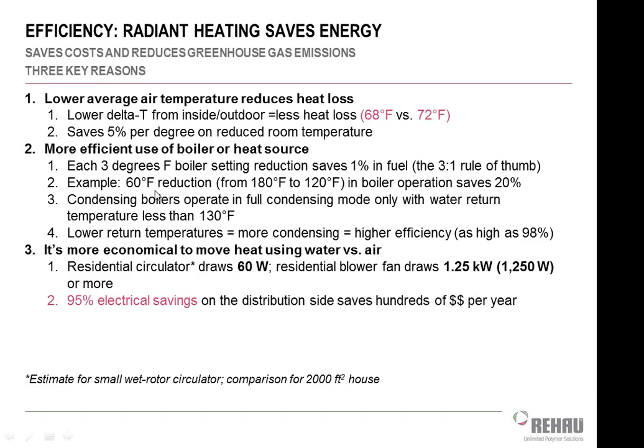The other thing we might want to mention, other than the gas saving discussion we had just a minute ago, is on the electrical side of the equation: pumping water in almost every single scenario is much less expensive than blowing air with a fan, regardless of how efficient your fan is and how great of an ECM motor you have. And then you could say, well, I have these very fancy variable speed ECM residential fans that are only costing me whatever, $100 a year to run. Well, the pump guys do the same thing now. They have variable speed ECM controlled pumps that do the same thing. So a typical residential circulator may draw 50, 60 watts of power, but if you use one of those ECM ones, you're drawing something like 8, 10, 12 watts. So it's the same kind of concept, but the pump is always going to be a better way to move energy than a fan for both residential and commercial. So you can save quite a bit on the electrical side of the equation as well.